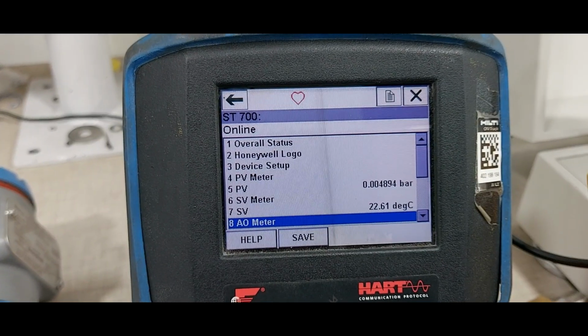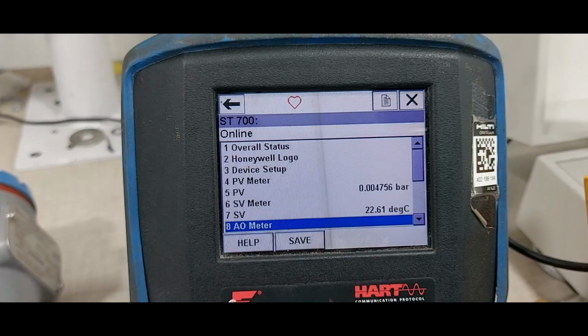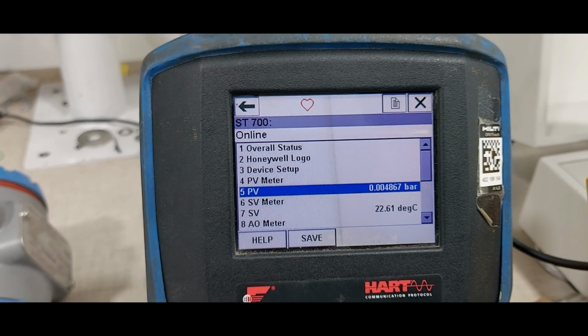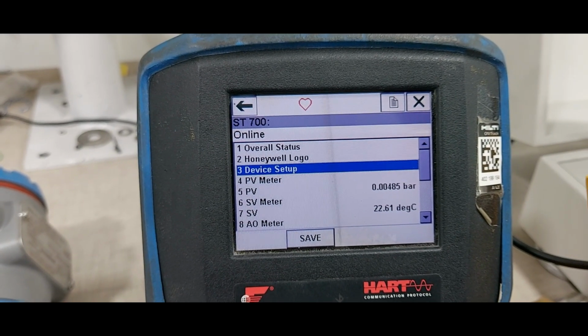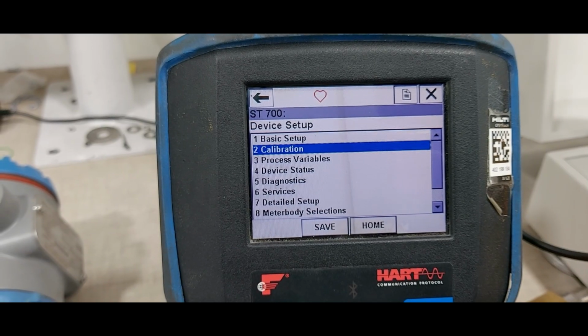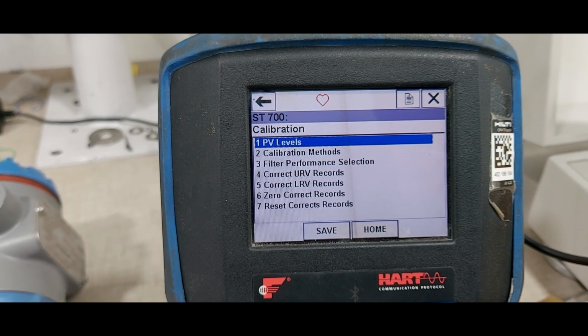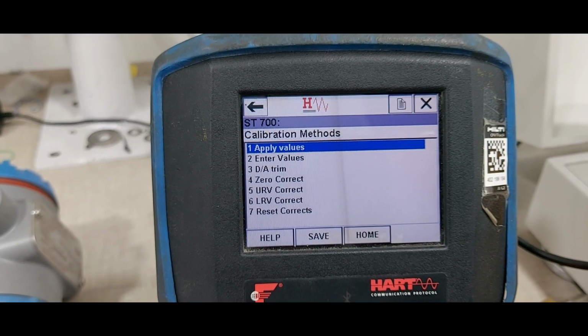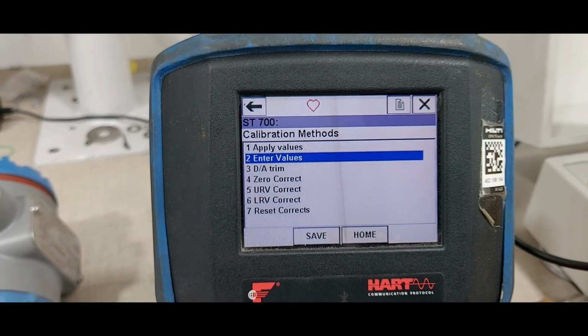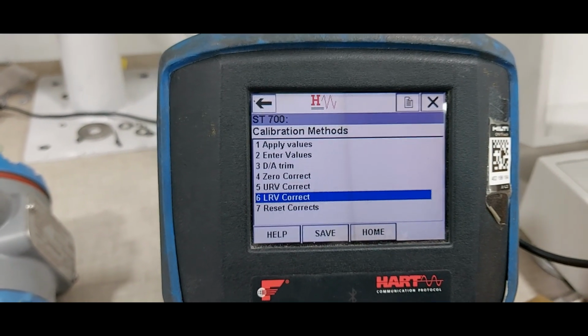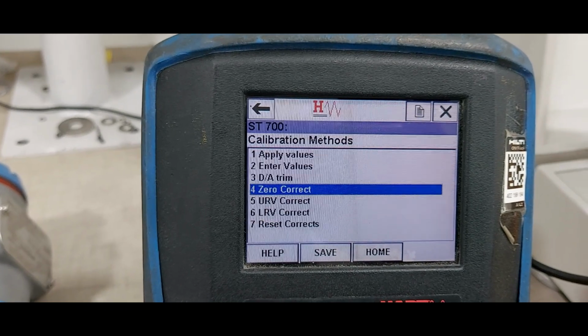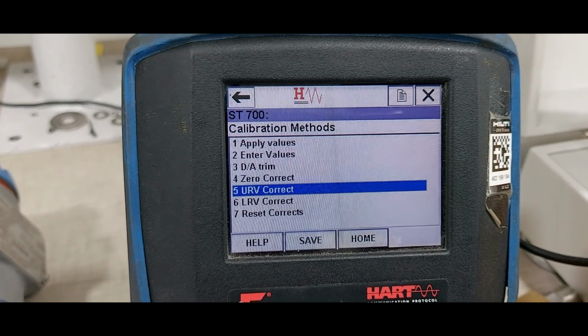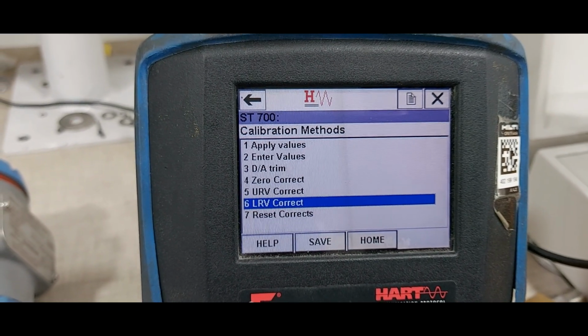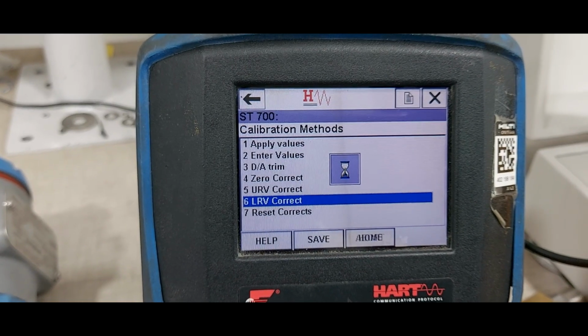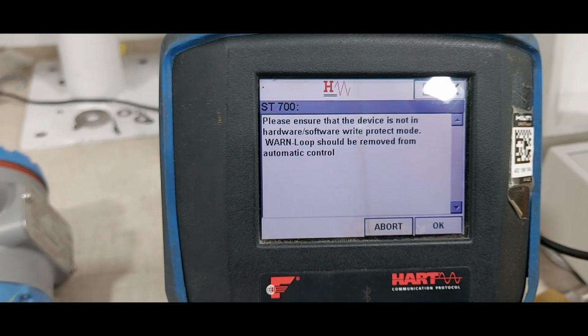First we are doing the calibration of transmitter 0 to 10 bar. First we are going to the device setup, calibration menu, calibration methods. LRV correct, URV correct, zero correct. Okay, first we are selecting the LRV correct. Select number 6, then press OK.